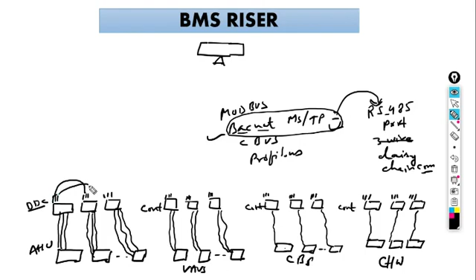Now, how are these things going to connect? There are 3 wires: one is plus, one is minus, and one is earthing, that is 0. So from plus to plus, from minus to minus, and from earthing to earthing. Again from here, plus to plus, minus to minus, and this to this. In this manner they are going to be connected. Now I am going to draw a single line so that you can understand: in, out, in, out, in, out. This is the BACnet MS over TP connection with the RS485 port.